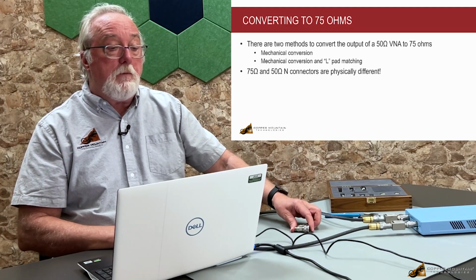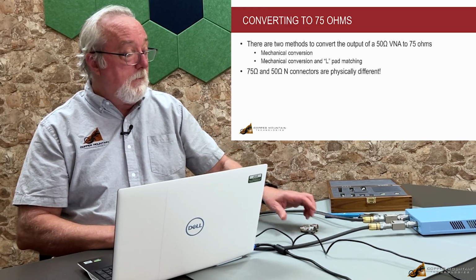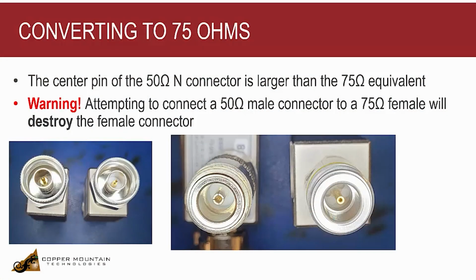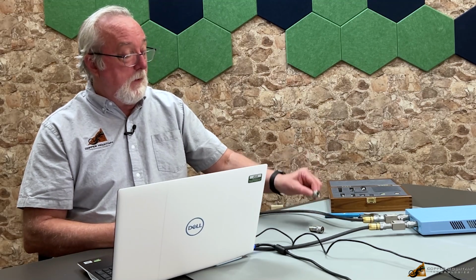And 75 and 50 ohm N connectors are physically different. So let's be very clear about this. The center pin of the 50 ohm N connector, that's this side, is larger than the 75 ohm equivalent. Warning, attempting to connect a 50 ohm male connector to a 75 ohm female N connector will destroy the female connector. So it's very important to understand which side of your converter, your L pad or your mechanical converter, is 50 and which side is 75 ohms. You can tell by looking at it. As you can see in the picture here, the 75 ohm connector has a much smaller female, and the 75 ohm male has a much smaller pin.